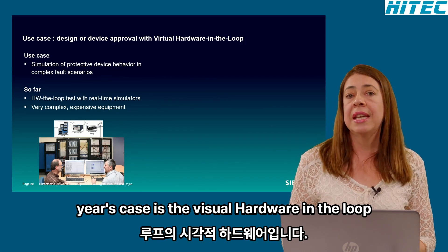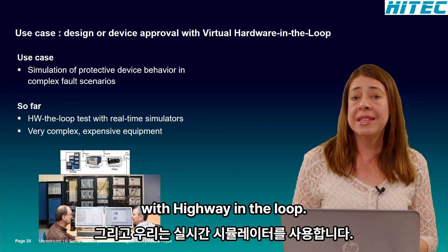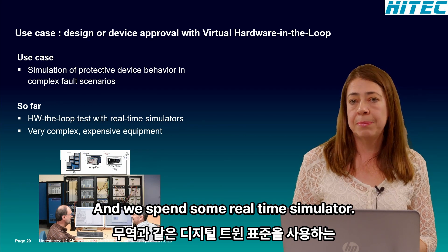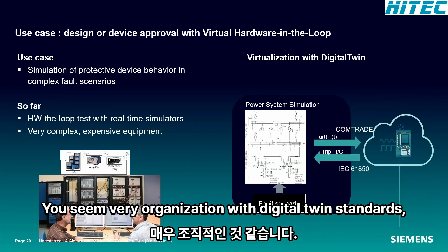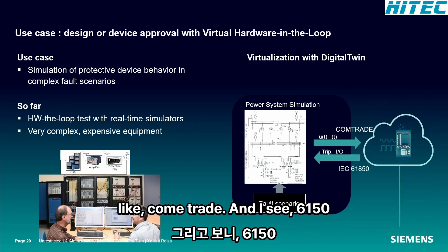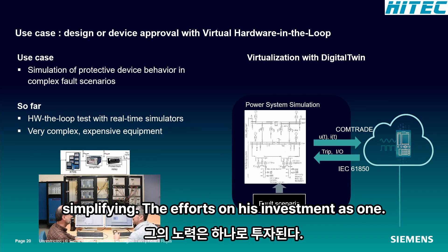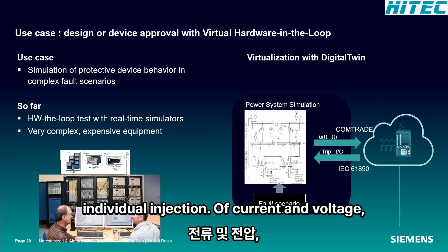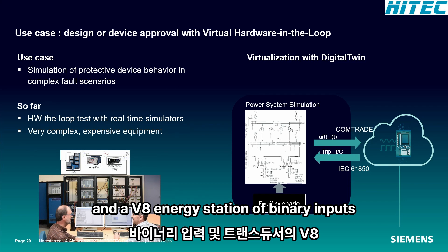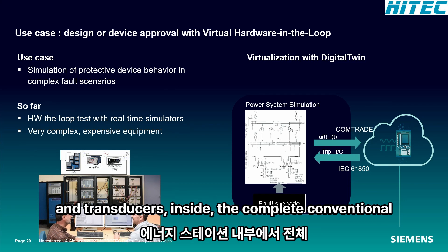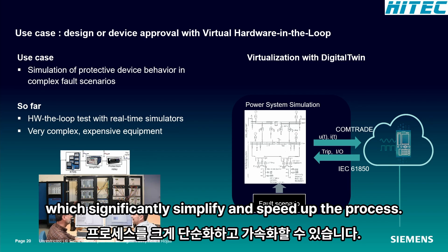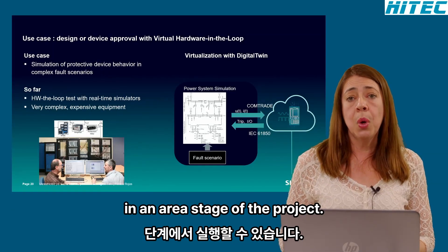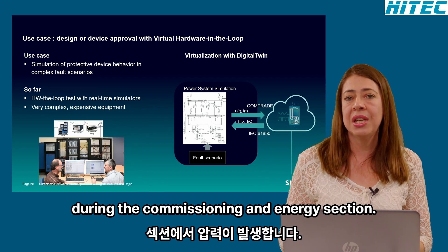The last use case is virtual hardware in the loop. Complex scenarios of protection are typically evaluated with hardware in the loop and with expensive real-time simulators. Using virtualization with the digital twin and standards like Comtrade and IEC 61850, the core simulation environment is ready, simplifying efforts and investment. Some testing equipment manufacturers, like Megger, are already working on virtual injection of current and voltage and virtual energization of binary inputs and transducers, replicating the complete conventional testing in a virtual environment. This test procedure can be run in an early stage of the project, reducing the time pressure normally experienced during commissioning and energization.